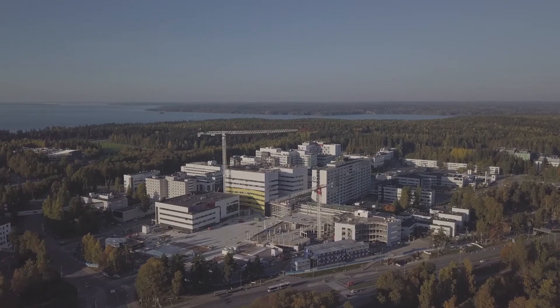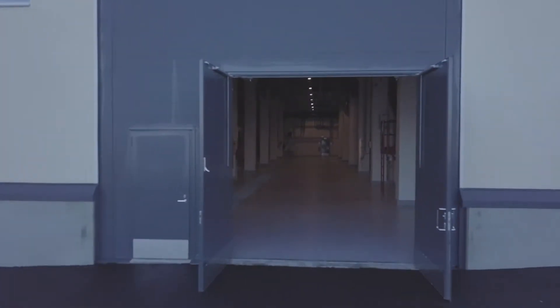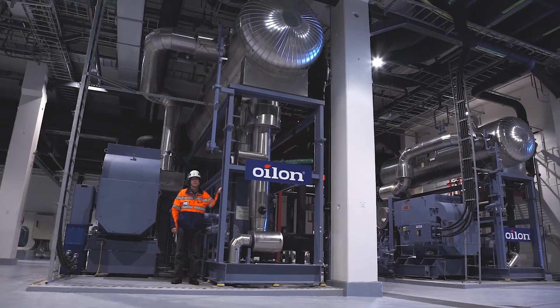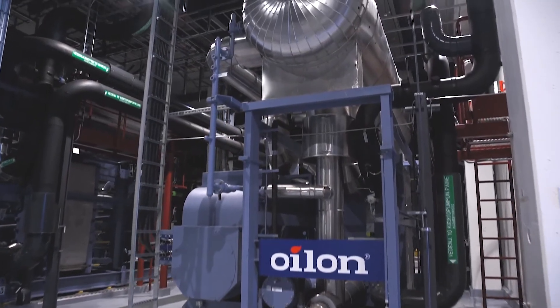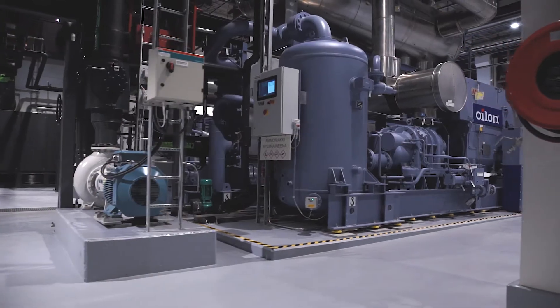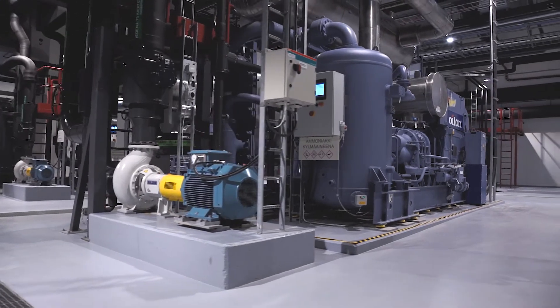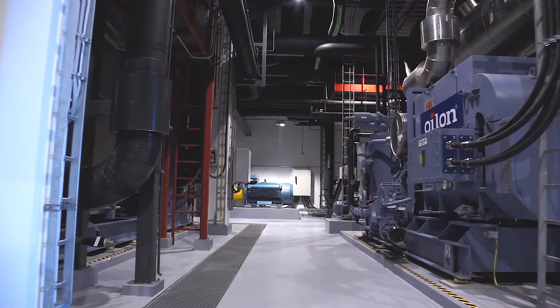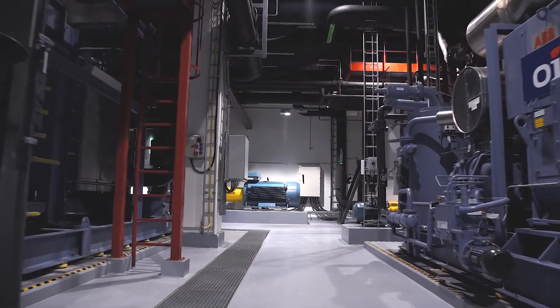All the customers receive cooling from Kaupin Oja's new, energy-efficient district cooling plant. Approximately half of the year, the highly energy-efficient cooling comes from the deep waters of Lake Nasijärvi. For the other half of the year, mechanical assistance is required for cooling. The two large water coolers and auxiliary equipment supplied by Oilon can produce 10 megawatts of cooling with an extremely high COP.